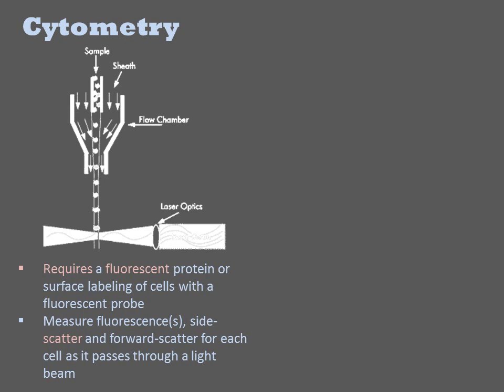The wavelength of that emitted light will be red-shifted relative to the laser's wavelength, so it is easily detected. Additionally, the cell will scatter the laser light in directions other than its original vector. These signals are quantified by placing detectors at alternate angles to the incident beam. Thus each cell gives a side-scatter signal, a forward-scatter signal, and one or more fluorescent signals depending on the instrument setup.